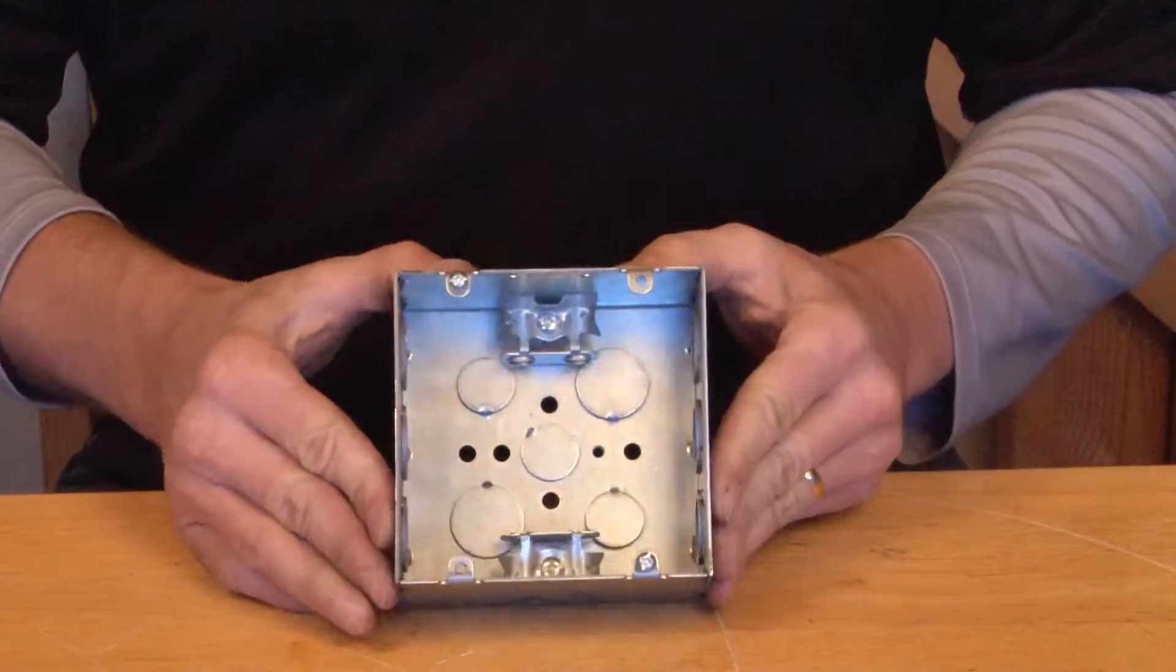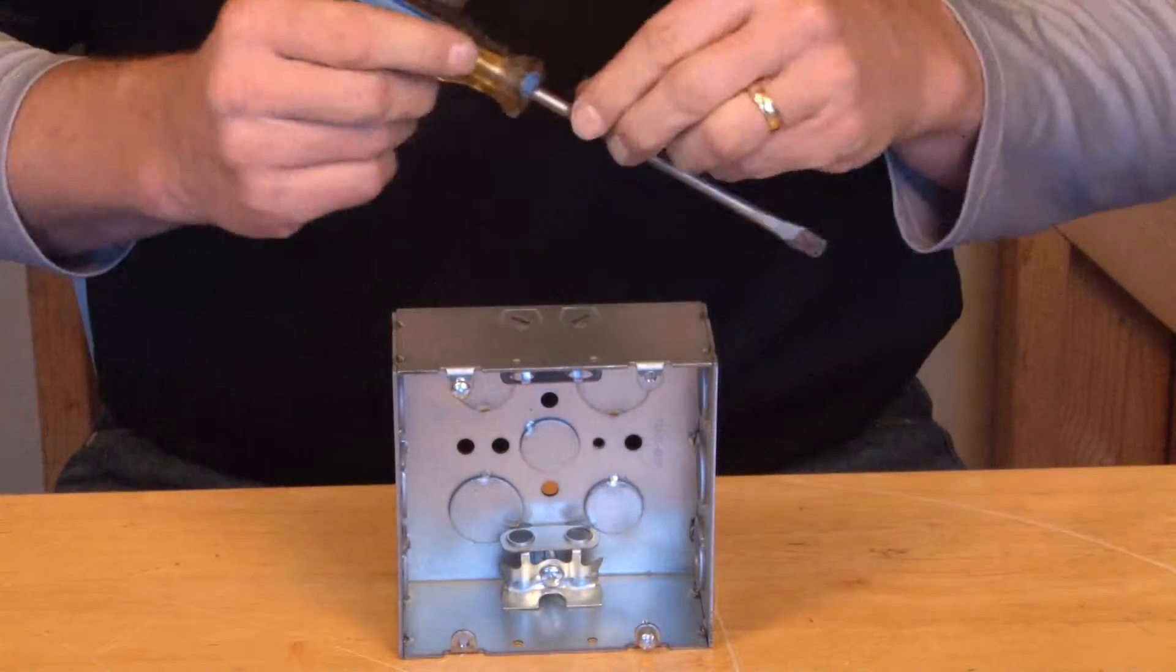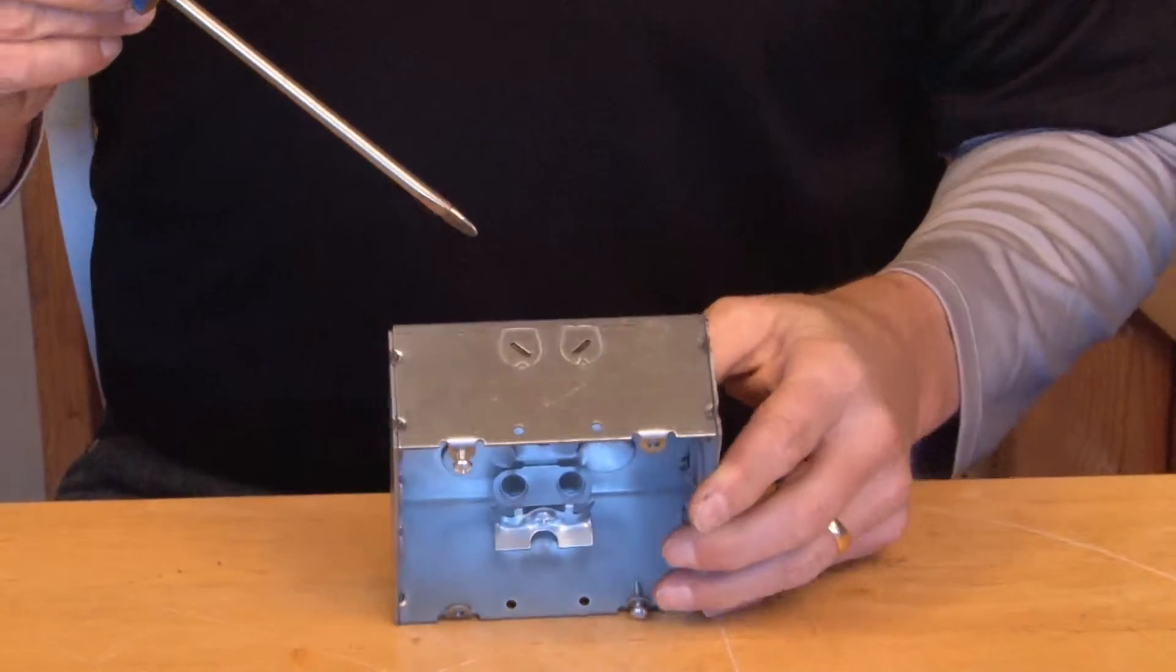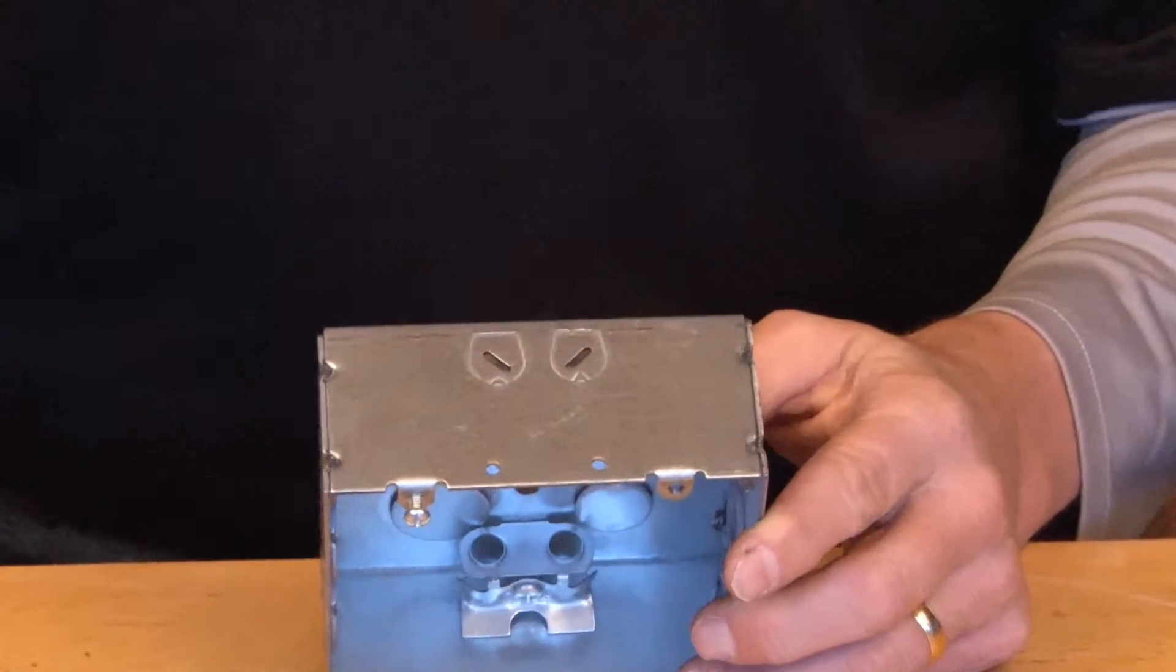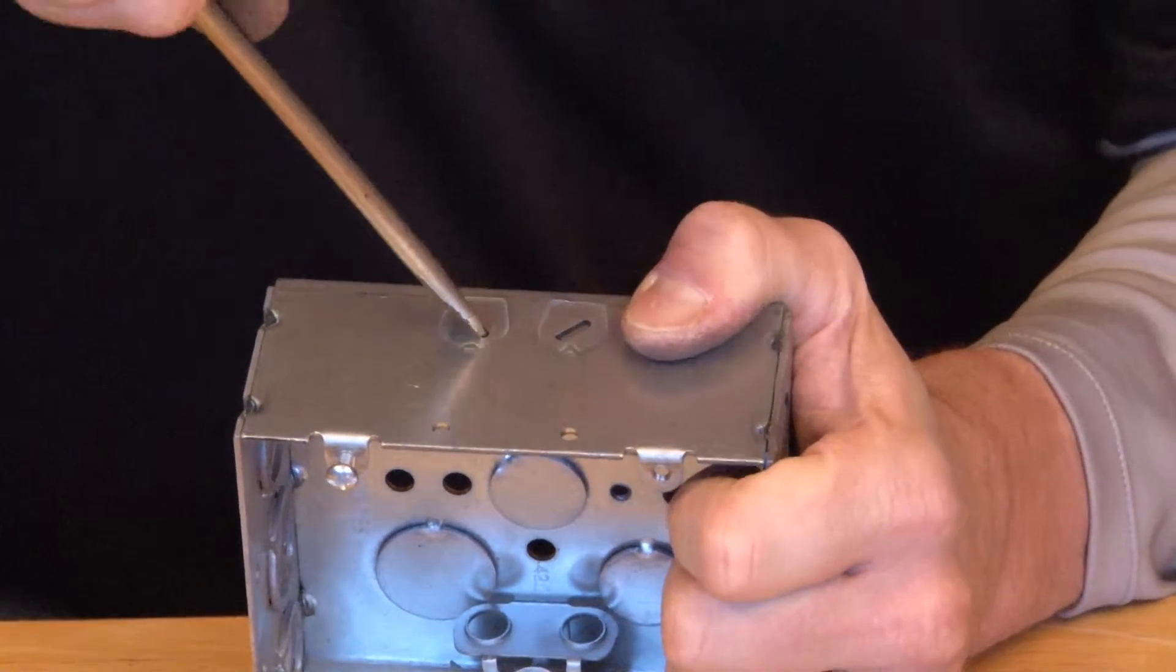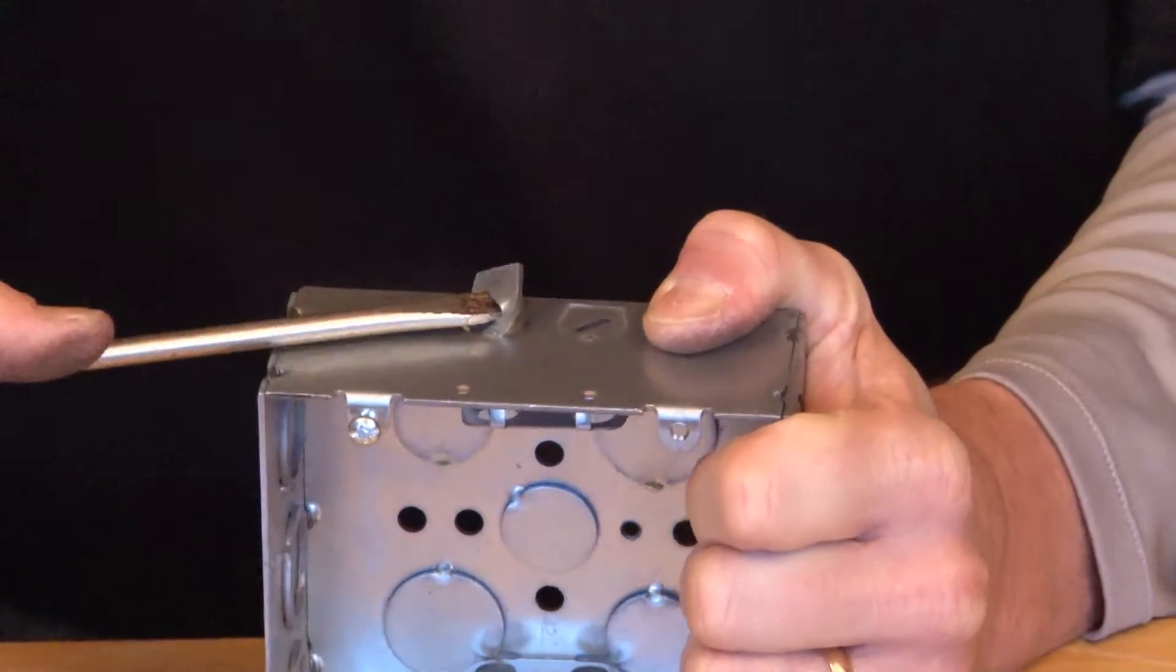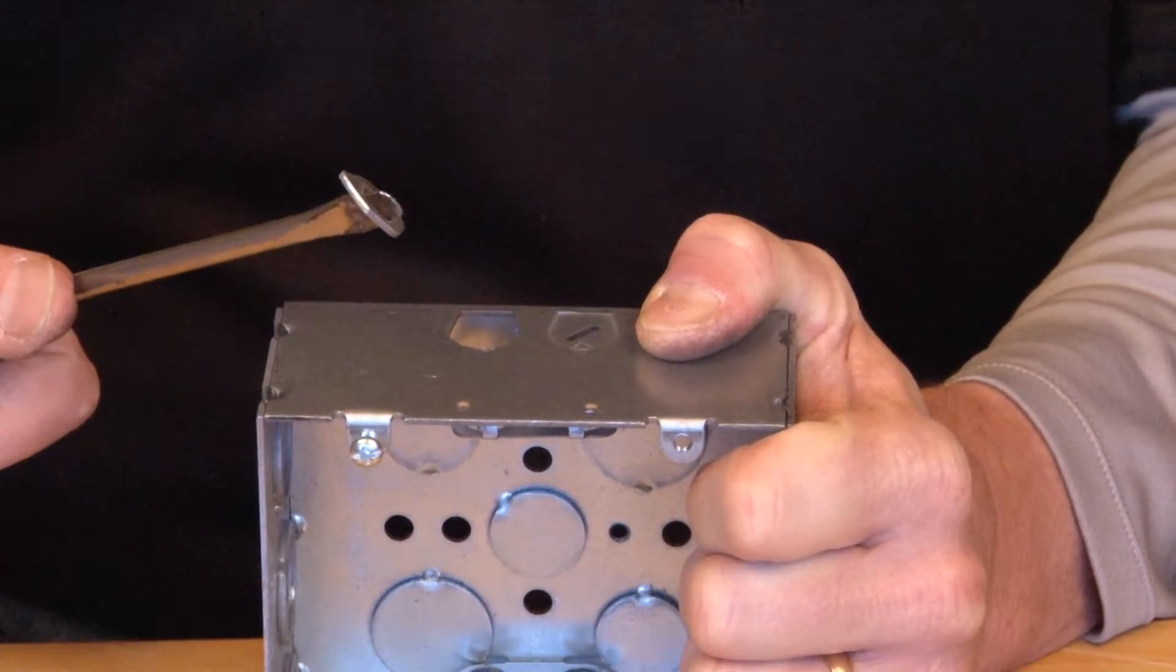When installing BX or flexible metal cable in this box, you simply take your screwdriver and remove one of the slugs quickly and easily by twisting. As you can see, it pops up quick and easy. You bend it back the other direction and it comes right out onto the screwdriver.